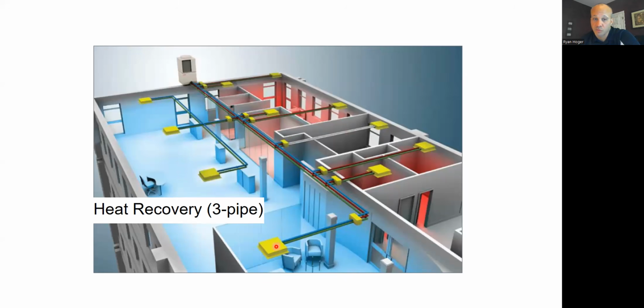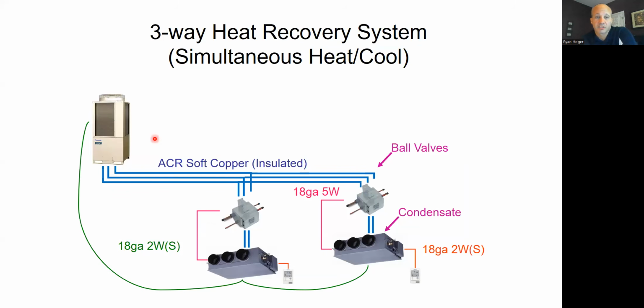Sometimes you'll have a one-to-one relationship. Sometimes you'll have this box switching for all three of these guys because it's just one big room. And the only reason I have three of them is just to get good distribution in this space. So I'm not putting all the cooling in one corner only. But as far as modes go, I'm never going to want him in cooling while he's in heating, so they can share a box. Schematically, everything looks the same as before, except I have three pipes running down the building instead of two. And then I added this switching box over here where three pipes come in, two pipes go out. Everything else is the same as it was a minute ago.